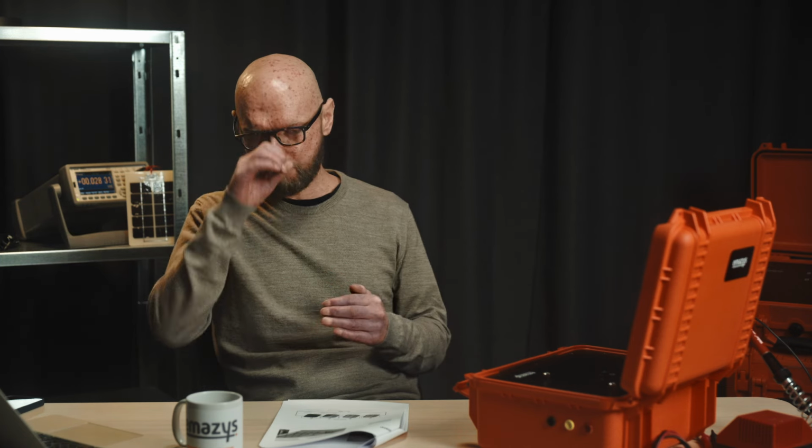It's very hard to say specifically what is the most common environmental or external factor, but definitely if you have a big PV system in a moist area, you're going to see a lot of ground faults, and there tends to be more rodents gnawing on the cables. So isolation faults are going to be something very important, especially in the northern hemisphere where you have a lot of moisture. You don't always have ideal weather. In that case, it's a mix of all these top 5 issues.